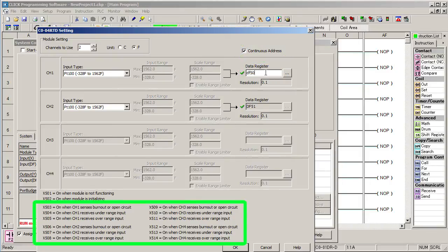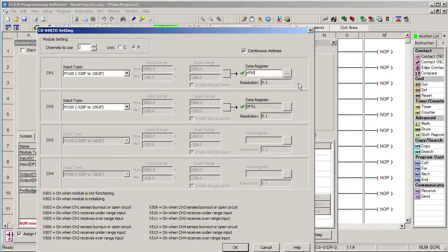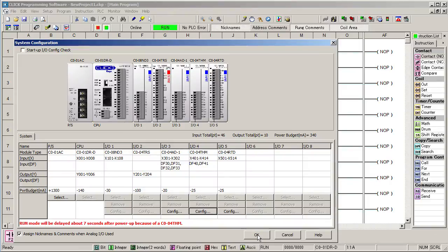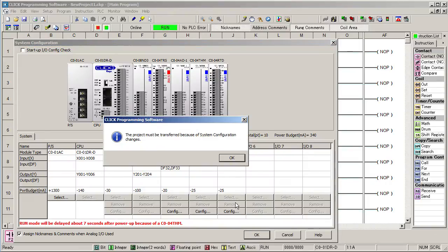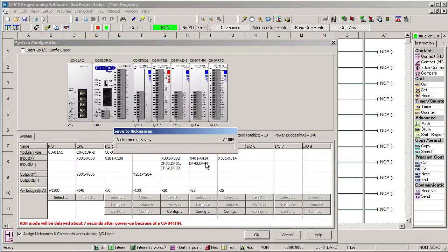Again, on this module you can read these input values to determine if the sensor is open or under or over voltage. And you can detect whether the module is initializing or not functioning. Don't ignore those. They can be real handy when you are trying to debug things. Well, that's it. We just configured 7 temperature measuring subsystems in about 2 minutes.